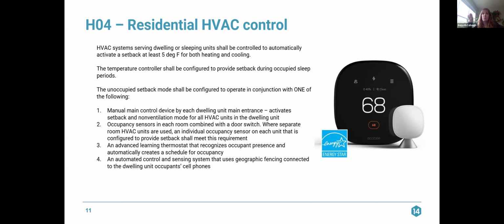Third option is an advanced learning thermostat that recognizes occupant presence and automatically creates a schedule for occupancy. You see a little example there of one of those thermostats, and it has the occupancy sensor you can put in your house. And then an automated control and sensing system that uses geographic fencing connected to the dwelling unit occupants' cell phones, and then sets back when the cell phone leaves the area of the unit. I thought that one was very interesting. I'd never heard of that. So just basically ways to try and reduce the heating and cooling loads and the heating and cooling energy use that those units in the residential units are providing when no one is in the space or when occupants are sleeping.